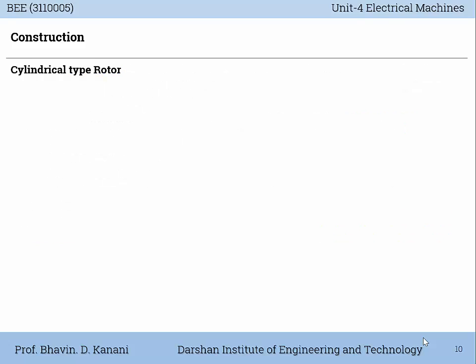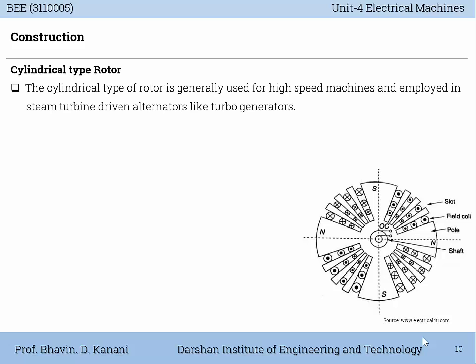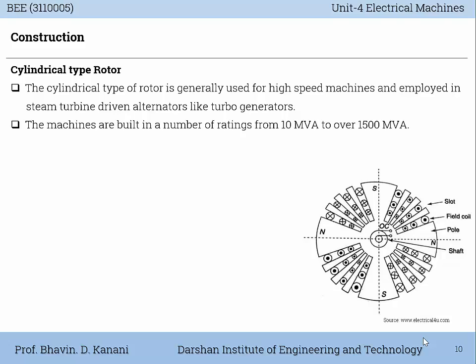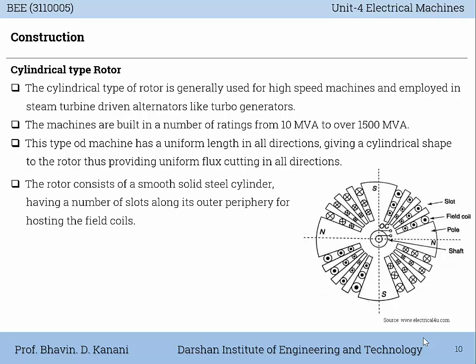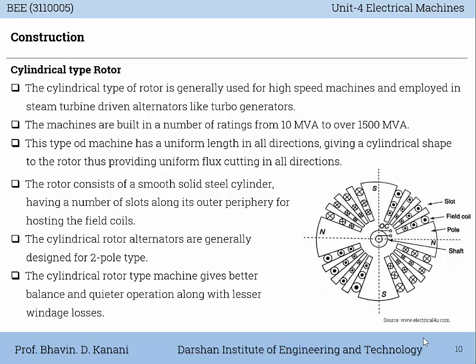Now the construction of the cylindrical type rotor is very well explained by this diagram. The cylindrical type of rotor is generally used for high speed machines and employed in steam turbine driven alternators like turbo generators. The machines are built in a number of ratings from 10 MVA to over 1500 MVA. This type of machine has a uniform length in all directions giving a cylindrical shape to the rotor, thus providing uniform flux cutting in all directions. The rotor consists of a smooth solid steel cylinder having a number of slots along its outer periphery for hosting the field coils. The cylindrical rotor alternators are generally designed for two pole types, and give better balance and quieter operation along with lesser windage losses.